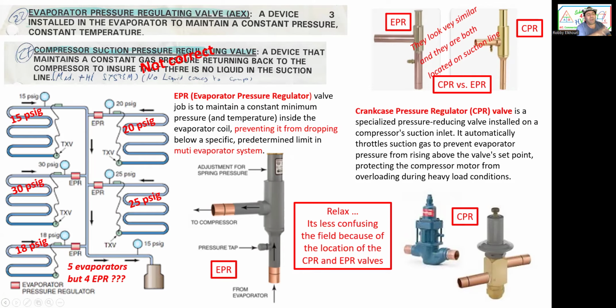As you see here, we have 5 evaporators, but 4 EPRs. Why 4 evaporator pressure regulators? Because the coldest one is not needed. The one running at 15 psig, we don't know what Freon this is, it looks like R134A. Whichever is the coldest, add 20 degrees and you get the temperature. So the coldest one doesn't need an EPR, but the other ones do, as you can see. The 18 psi does, the 25 has one, 20 and 30 have one, but the 15 doesn't. So whatever happens, the other 4 evaporators will never go below a certain temperature.